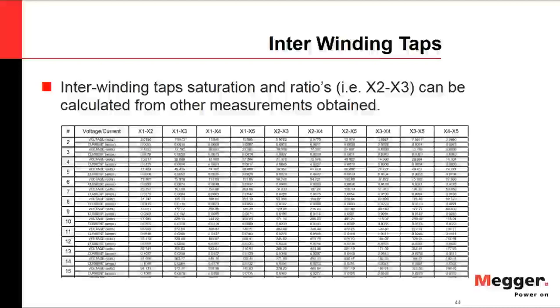Using the concurrent method, you can obtain saturation current and voltage values in a tabulated manner for every single subsection of your CT — from X1 through X5 and all inter-winding combinations.